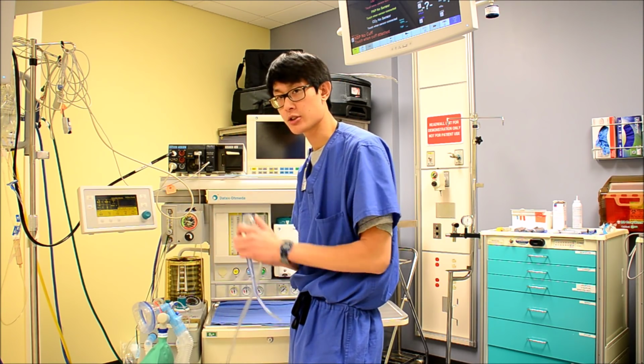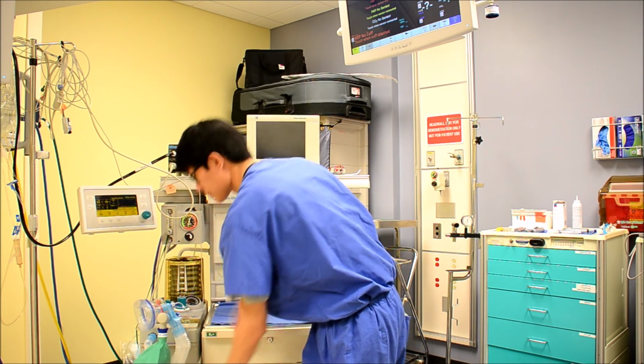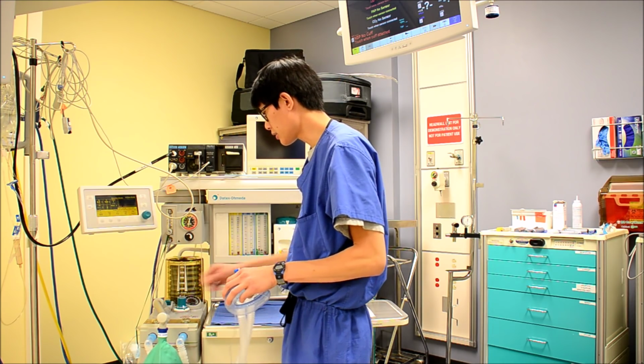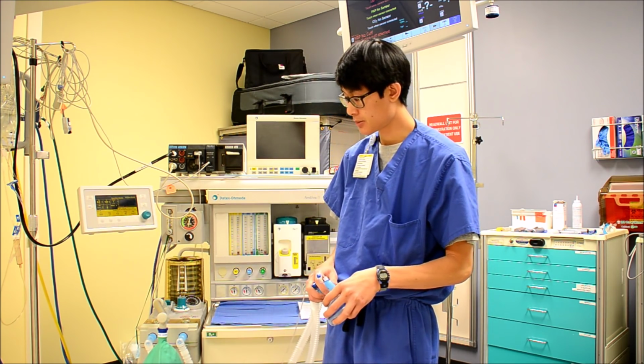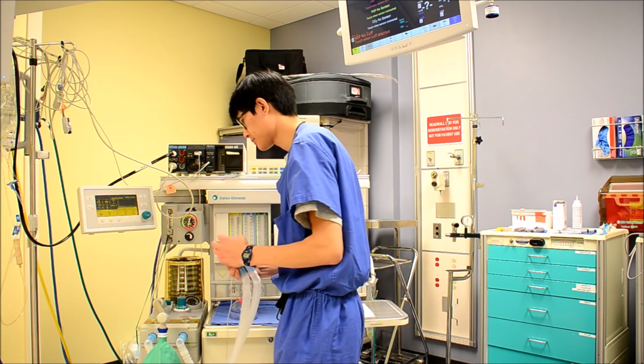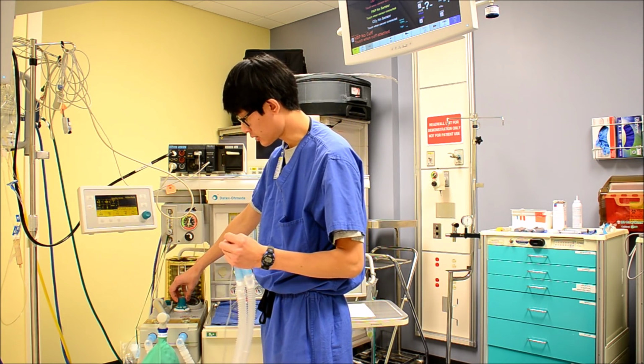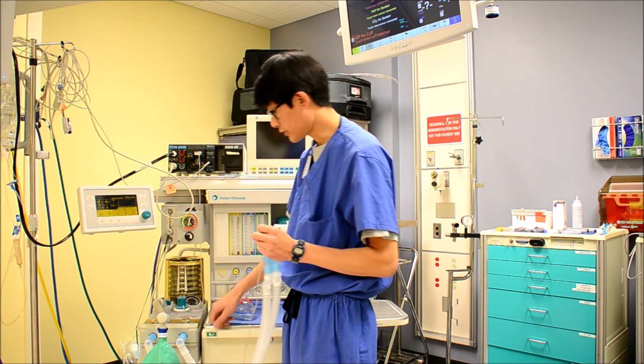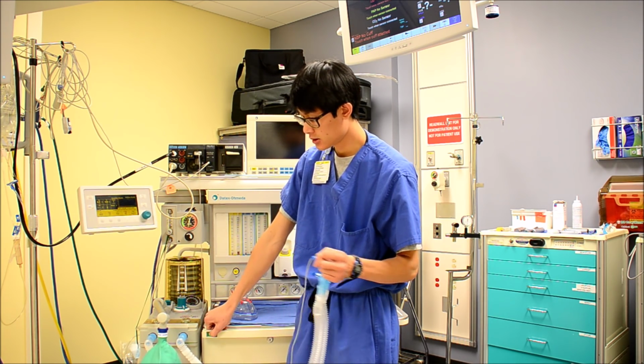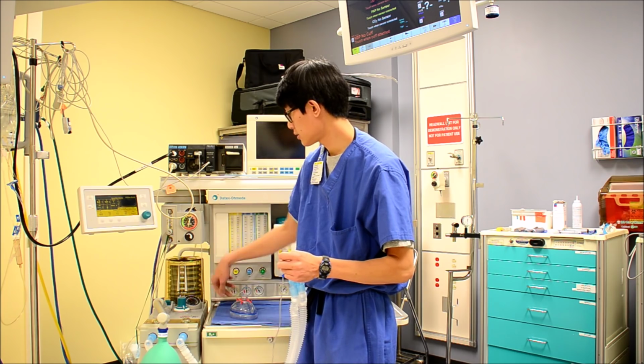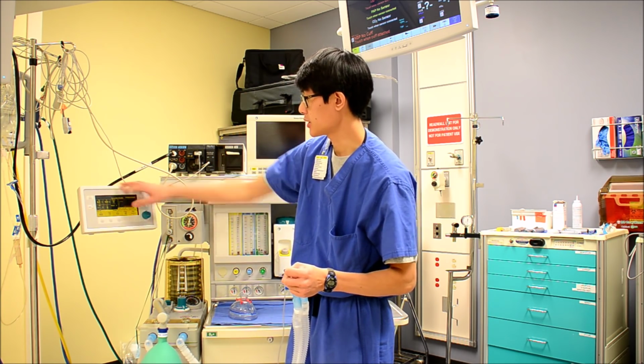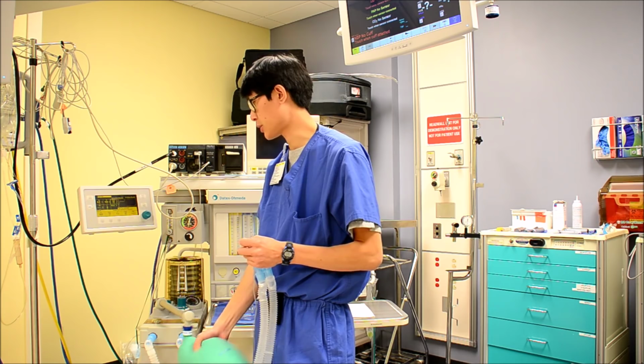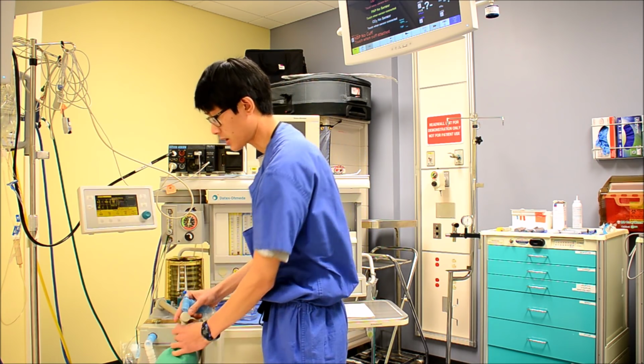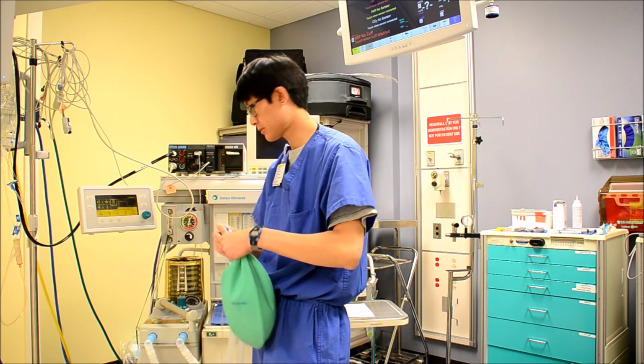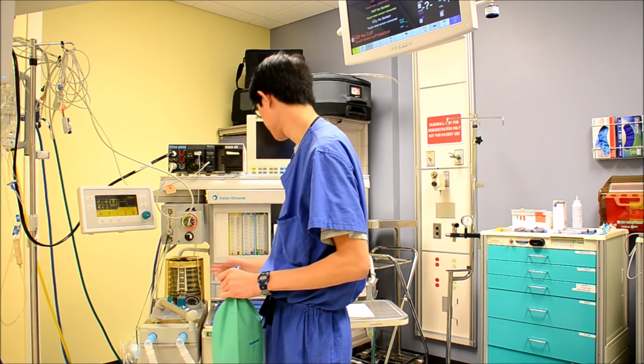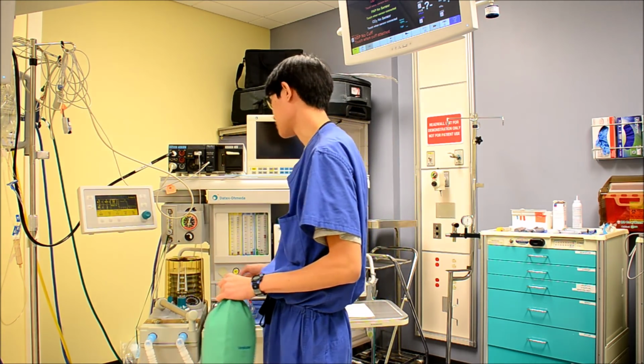That's usually the first thing I do, is just check suction is working, and it is. And like you did earlier, just to make sure your circuit is pressurized, include your Y piece, flip your APL to 70, hold pressure at 30, make sure you have an alarm, and it looks like we're pressurizing just fine. Take the bag off, make an artificial lung again, flip to vent mode, and we'll do the same progression.